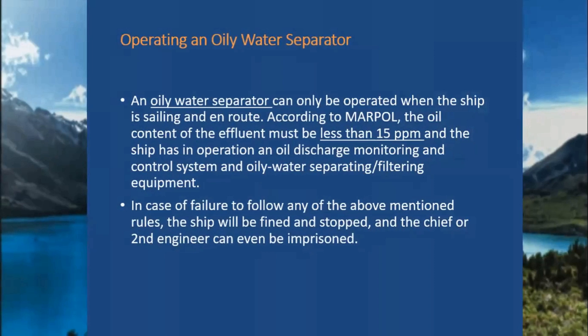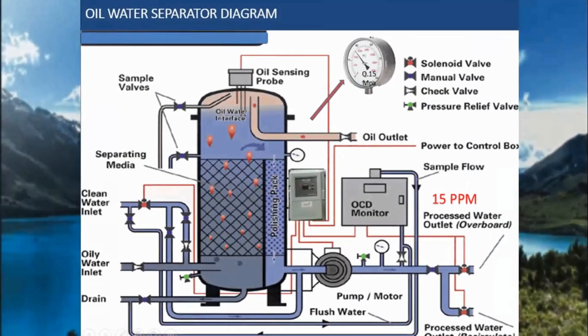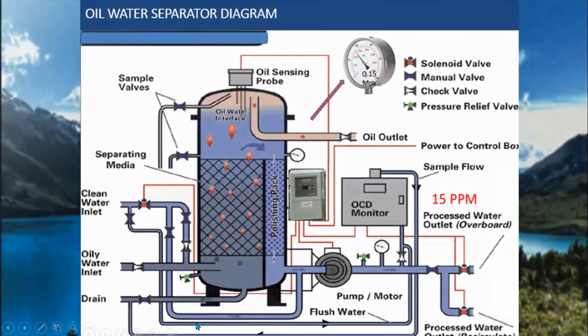The oily water separator can be operated when the ship is sailing in route. The oil content of the effluent must be less than 15 ppm, and the ship must have in operation an oil discharge monitoring and control system and oily water separating and filtering equipment. In case of failure to follow any of the above mentioned rules, the ship will be fined and stopped, and the chief or second engineer can be imprisoned.